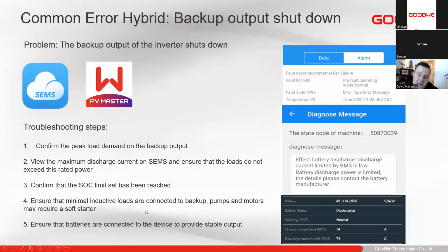And then lastly, we need to make sure we have batteries before we connect loads to the backup output. Sometimes we might not have batteries available and we install the system already, everything connected to the backup. When the grid is there and the solar is there, the backup is working. But as soon as the grid fails and there's any load increase, the backup shuts down. And we can damage the inverter by doing this regularly. So it's not advised to install backup loads if you don't have a battery connected to the inverter.